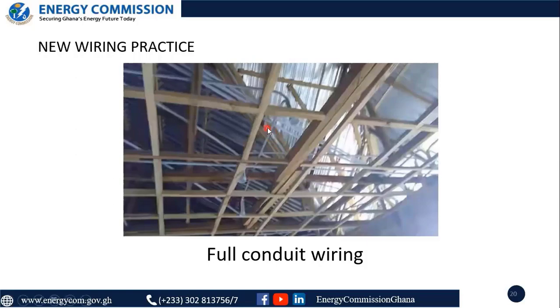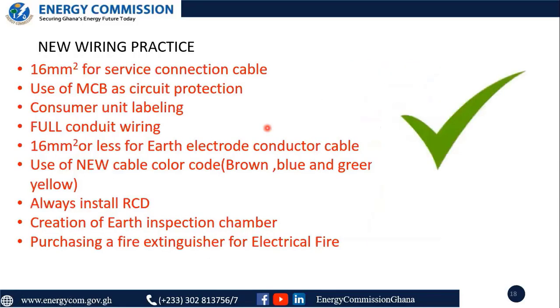Please, can we go back? Okay, so the installation of RCD, always, it's written there: always install RCD, always. Because today you might get a good earth resistance value, but tomorrow it might be bad. The RCD will compensate for that.